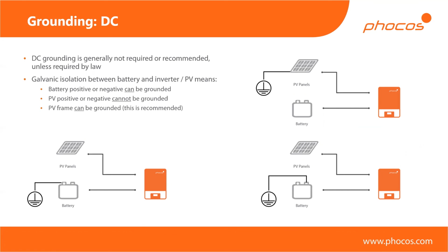Then for grounding the DC side, like I said, the only mandatory grounding is the ground on the AC of the inverter. The rest here is voluntary, or, depending on your legislation, it might be mandatory. The one thing that really does make sense to ground is the frame of your PV modules and the structure they're mounted on. This doesn't have any effect on the device whatsoever. You can ground your battery negative or your battery positive. For PV, you're not allowed to ground either positive or negative. So for the battery, you're completely free to ground as you wish. For PV, you can only ground the frame of the PV modules.